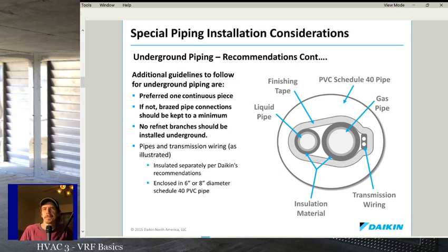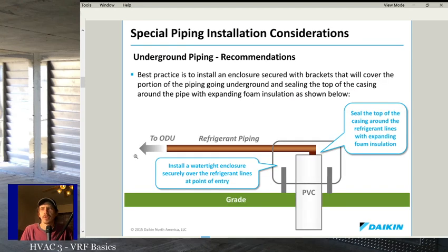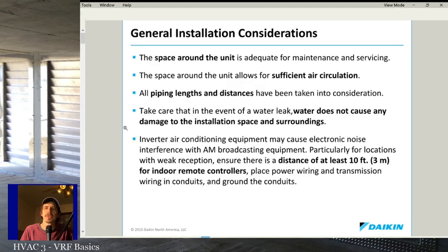The liquid line, the biggest reason for the liquid line being insulated is so you don't have heat loss through that huge run that you're going to have, because you're talking about hundreds of feet of liquid line. You will have heat losses in it, and the other two should be obvious because both could be suction at any time, and the discharge line could be hotter than you'd really want it to be. So there's a bunch of other rules there, but those are kind of the neat ones that might give you some things to think about the next time you're looking at refrigerant pipe and how to run it and what your options are.